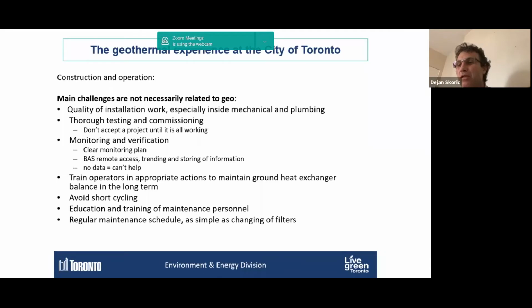Training operators is part of the design, part of the commissioning and monitoring plan. We have to enable operators to know what's going on. First, educate and train them, but also give them simple cheat sheets so they know what to do if a heat pump suddenly starts short cycling, or if the loop temperature goes higher than expected for that time of year. Are there simple actions they can take instead of letting it go until it's too late? This whole thing is about preventing the problem, and that's what we should aim for.